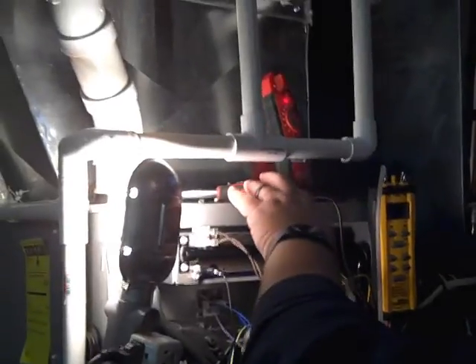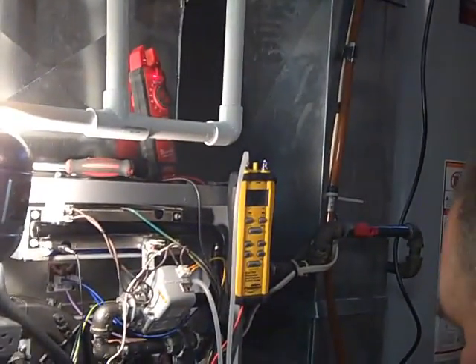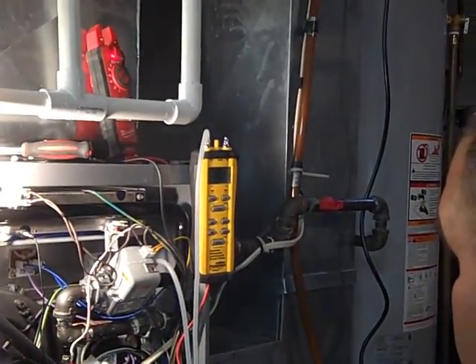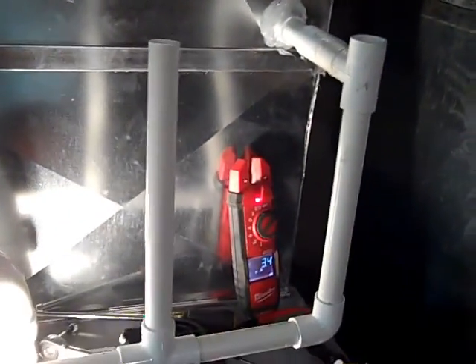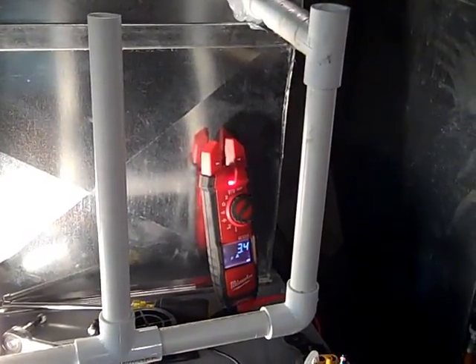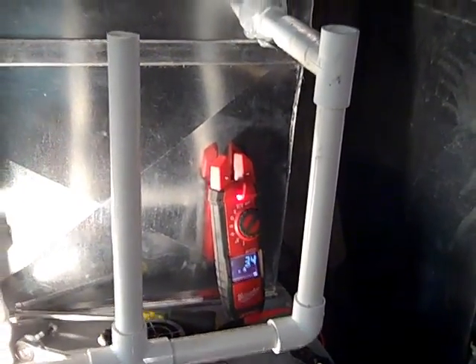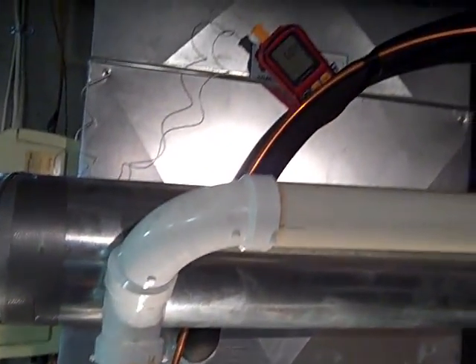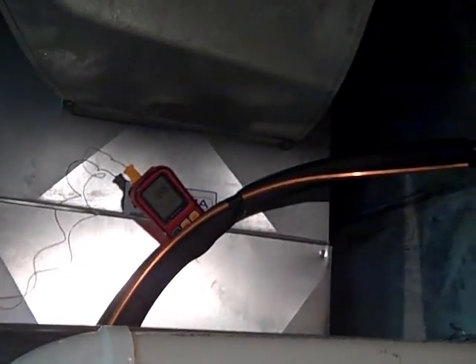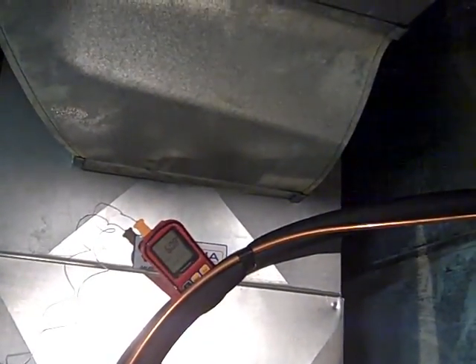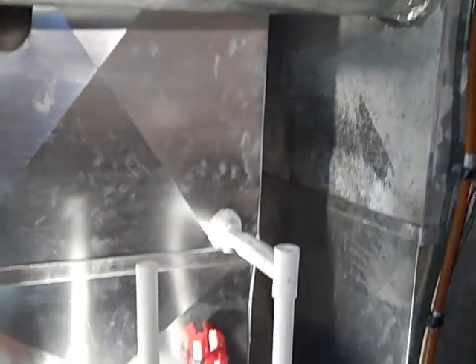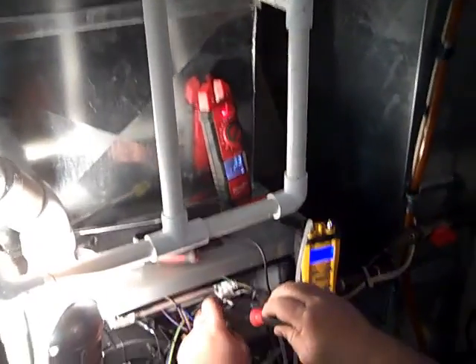Alright, well, now the furnace is on. Burners are back on. We see that we've got a dual port manometer that's connected up. We see we've got the multimeter connected so he can check his flame sensor reading. We see 3.4 on the microamperage on his flame sensor. And if we look up here, we can see that Kevin has got his thermometer set so that he can start taking temperature rise, because we need to know what the temperature rise is through here.